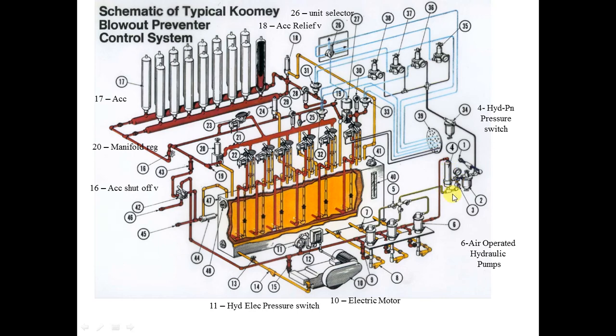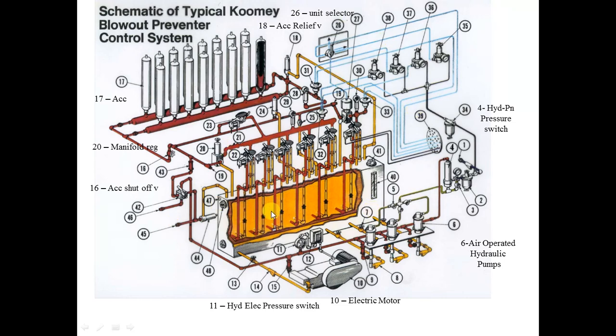This switch works for two types of fluids: air (pneumatic) and hydraulic oil. It is set on a value to protect the pump from high pressure. Any pump or system here must be protected by a minimum of double protection from high pressure. The first protection is the switches; the second is the relief valve.